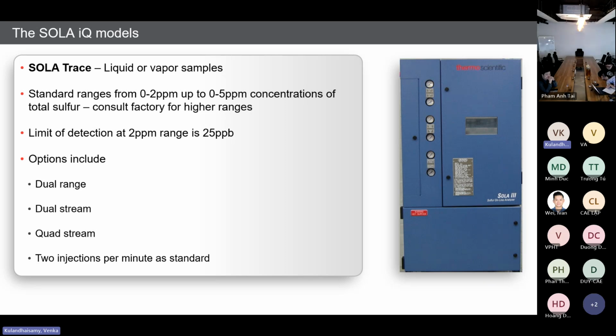So the standard range for the trace analyzer is 0 to 2 ppm, up to 0 to 5 ppm concentration of total sulfur. Actually, customers need to consult our factory for high ranges. If they want to measure a 0 to 10 ppm range, then the trace analyzer is not advisable. They have to go for a standard unit. If they want to measure below 5 ppm, then yes, they can go for a trace analyzer.